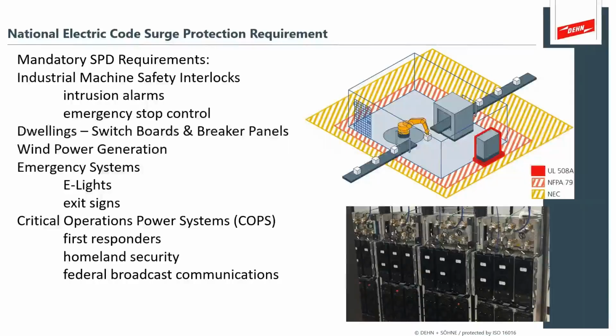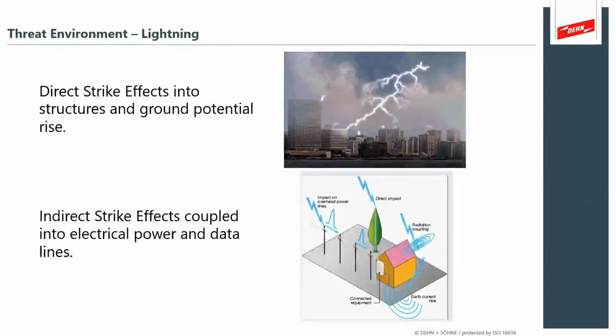And then the operations power systems at first responders, homeland security, federal broadcast, the emergency services, hospitals, fire and ambulance services all sit on a communications backbone that all have mandatory SPD requirements. So that's the type of things that have to have surge protection. But you'll see in industry that you'll want surge protection because of the environment. And so we've got a couple of quick descriptions of what the threat environment looks like.